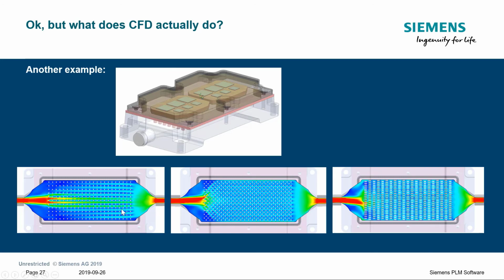Because the first one will be best cooled, where the liquid is still cool. The second one, the liquid is already a little bit hotter, and you want to have an equal temperature over all 3 of them. So how do you stack them? And for this, simulation is much better used because you can play with parameters, vary a lot of design parameters, and really create the optimum. And ideally, use an optimization tool.